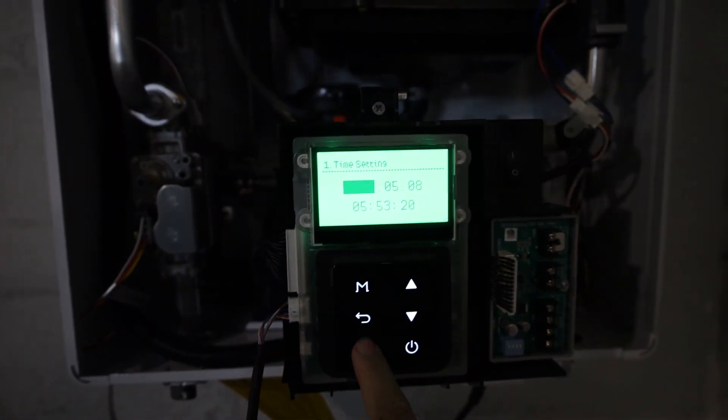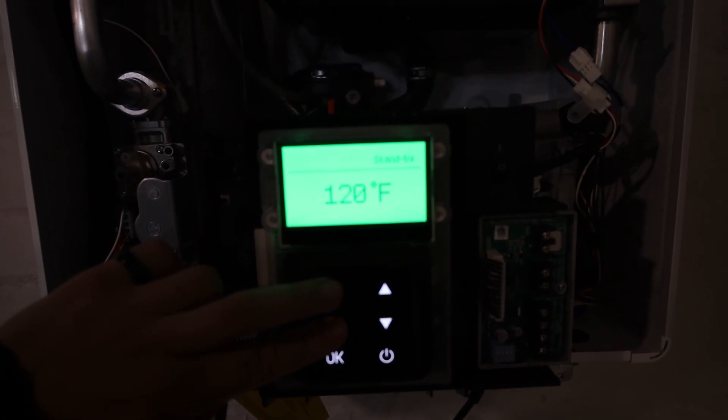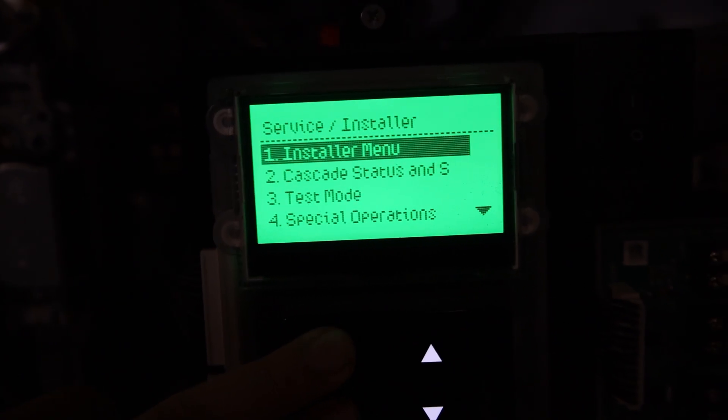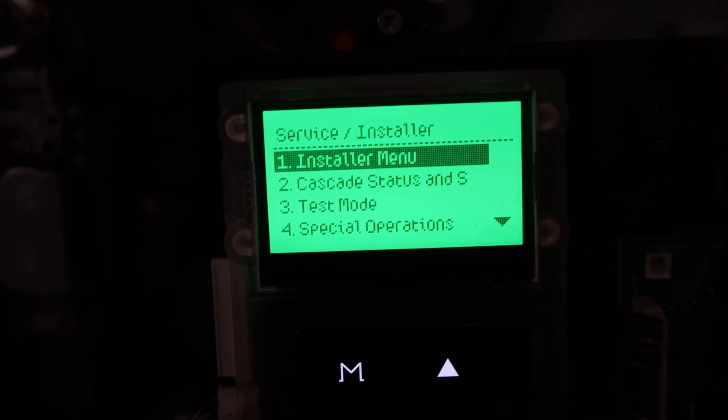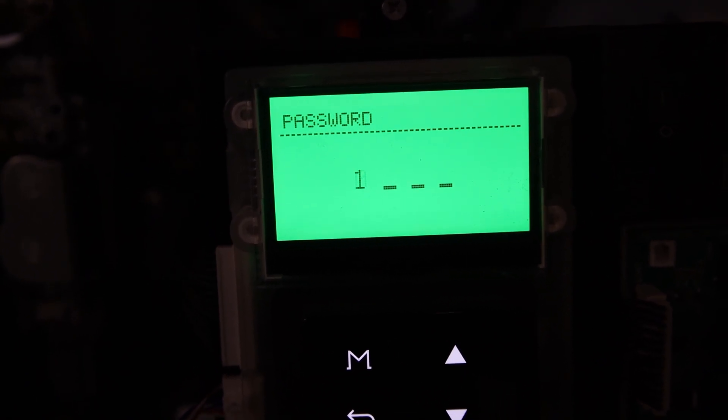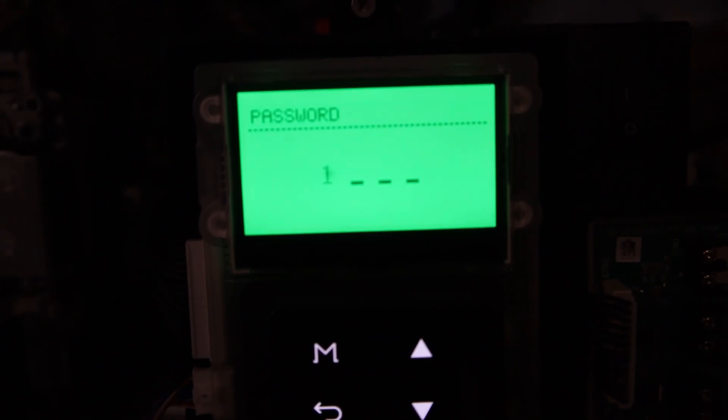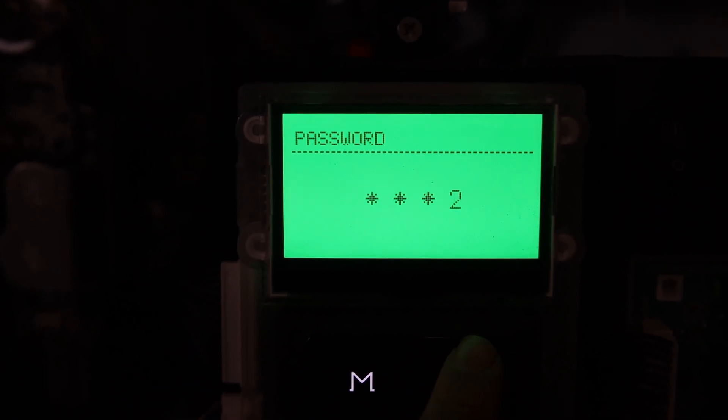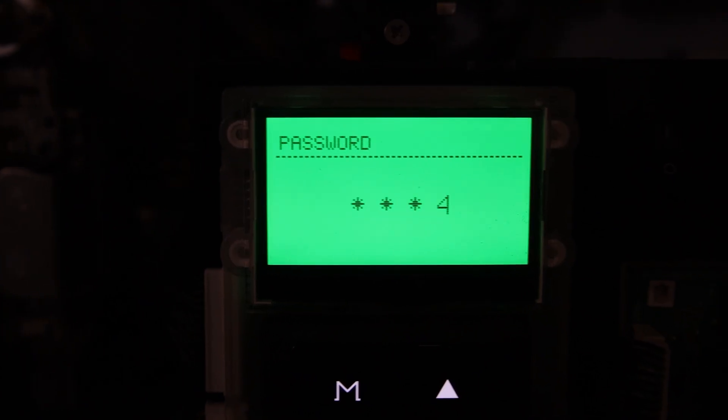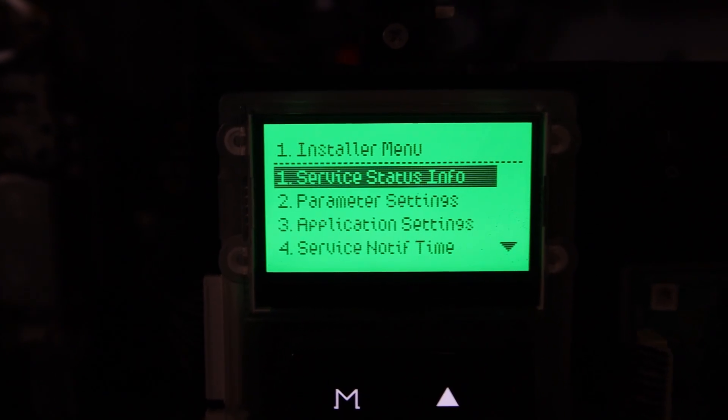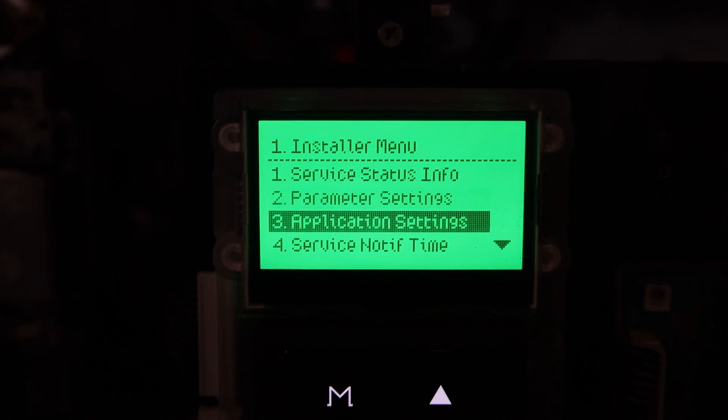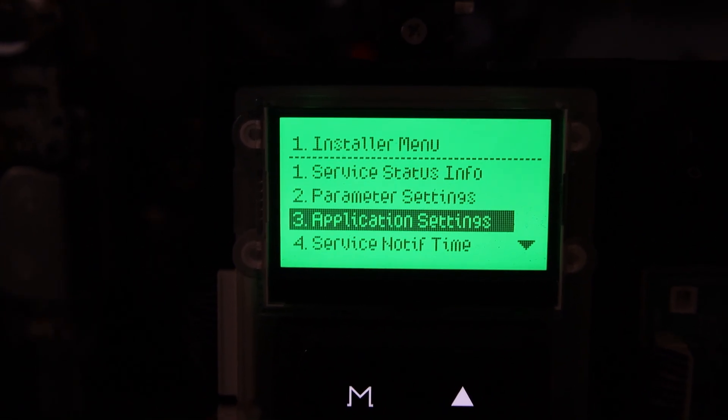Make sure you already did your setup wizard. If you haven't, do that first. Once you're on the screen with your set temperature, press the M and the back arrow at the same time for about five seconds. You're going to get into your installer menu, putting in your password of 1-2-3-4. Once you get in, go down to number 3, your application settings.